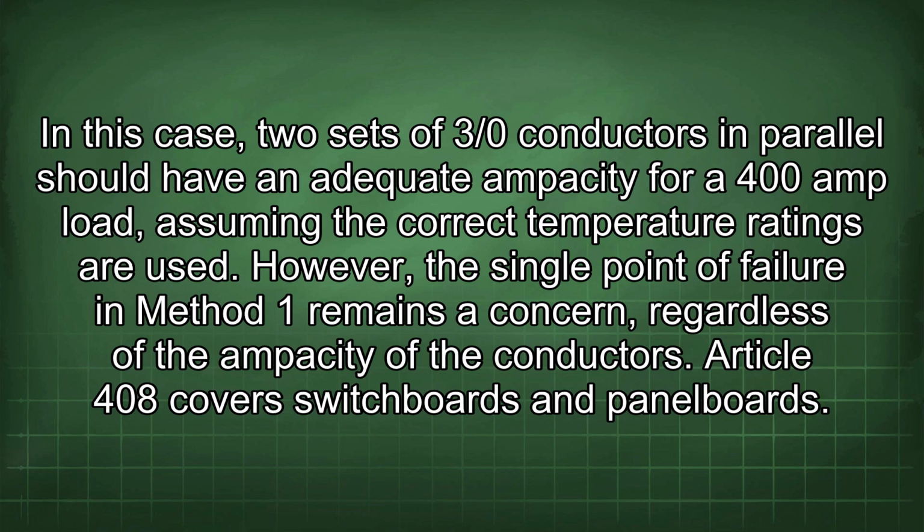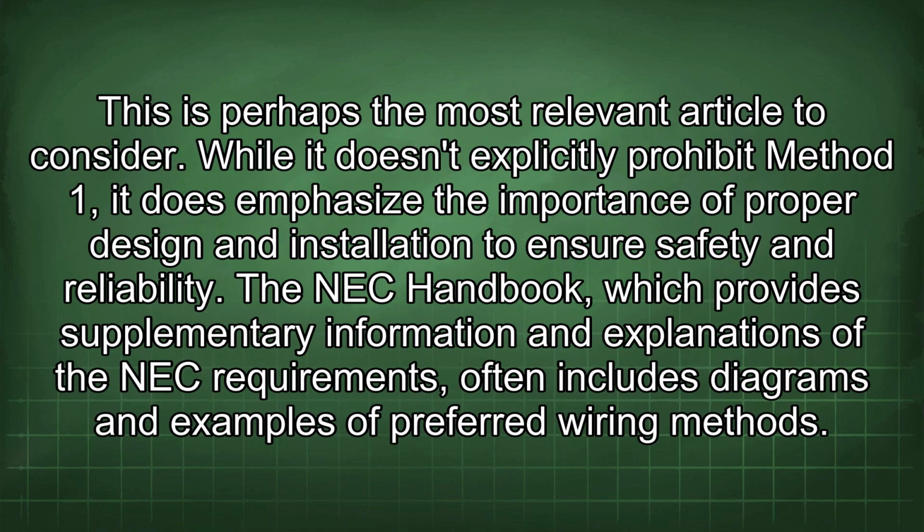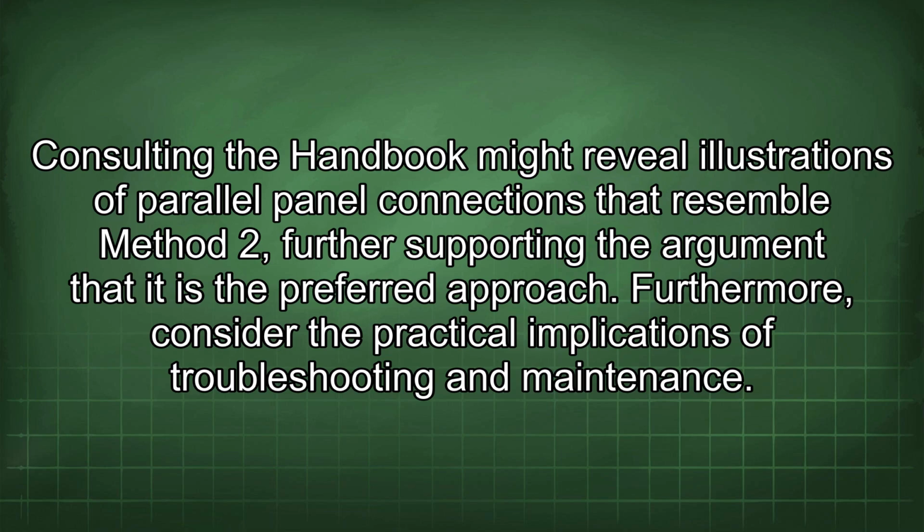Article 408 covers switchboards and panelboards. This is perhaps the most relevant article to consider. While it doesn't explicitly prohibit Method 1, it does emphasize the importance of proper design and installation to ensure safety and reliability. The NEC Handbook, which provides supplementary information and explanations of the NEC requirements, often includes diagrams and examples of preferred wiring methods. Consulting the handbook might reveal illustrations of parallel panel connections that resemble Method 2, further supporting the argument that it is the preferred approach.